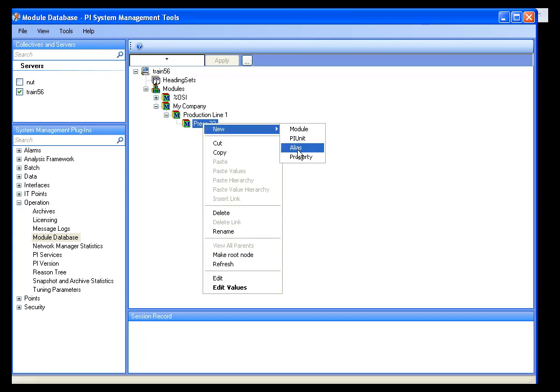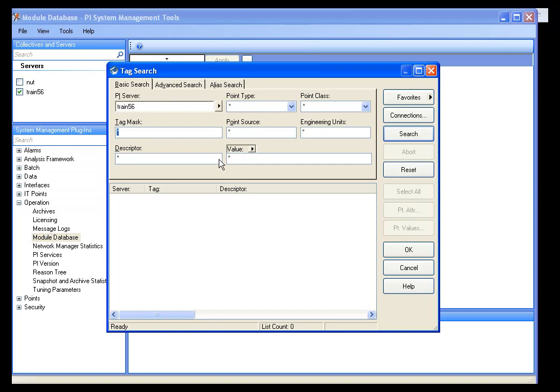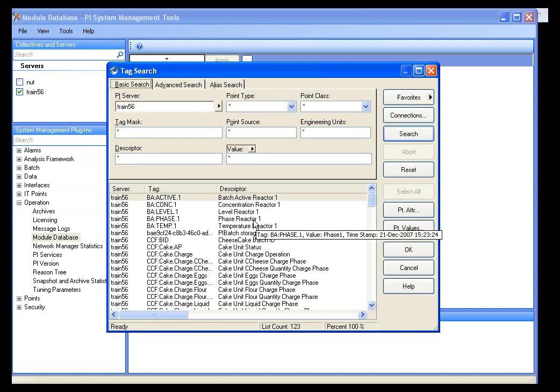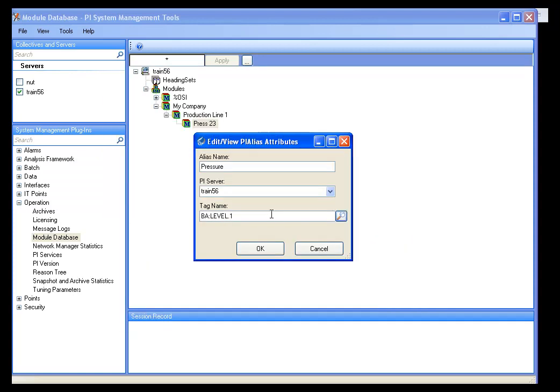The first thing I want to do is tie an alias to this module. I will right-click and select Alias. The alias I am going to use is called Pressure, and I have a certain hydraulic pressure that is associated with this press. I can either select my PI Server and type in my tag name, or I can use the Tag Search button and use the familiar Tag Search functionality that most people who use PI are familiar with. I am going to use one of my random tags — my BA level tag — and tie it to this.